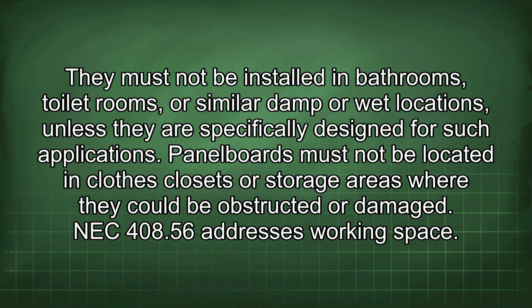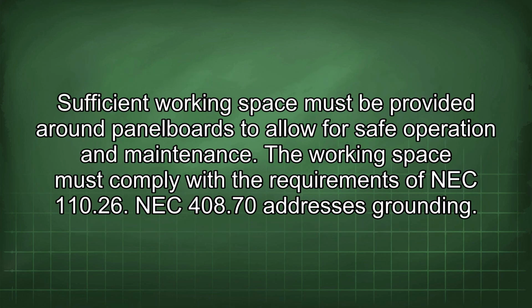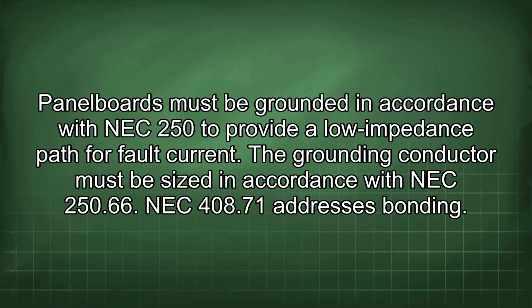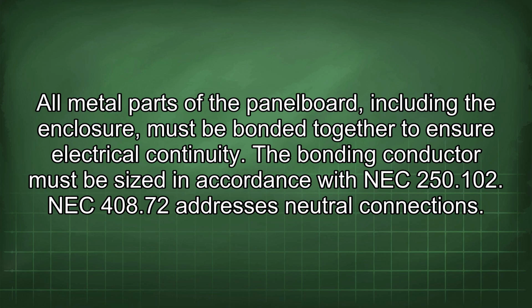NEC 408.56 addresses working space. Sufficient working space must be provided around panel boards to allow for safe operation and maintenance. The working space must comply with the requirements of NEC 110.26. NEC 408.70 addresses grounding. Panel boards must be grounded in accordance with NEC 250 to provide a low impedance path for fault current. The grounding conductor must be sized in accordance with NEC 250.66. NEC 408.71 addresses bonding. All metal parts of the panel board, including the enclosure, must be bonded together to ensure electrical continuity.